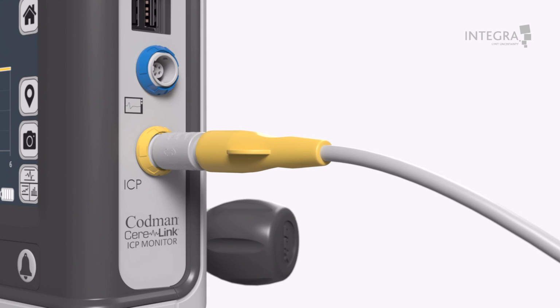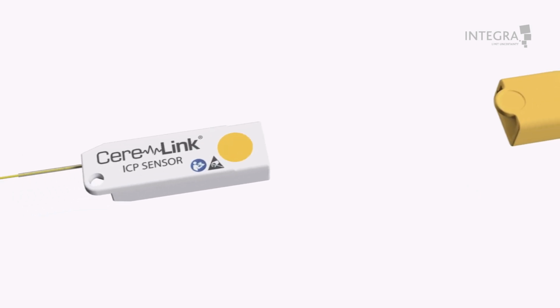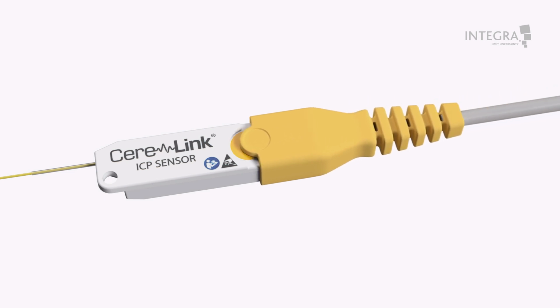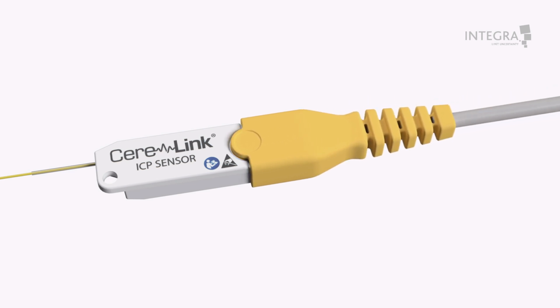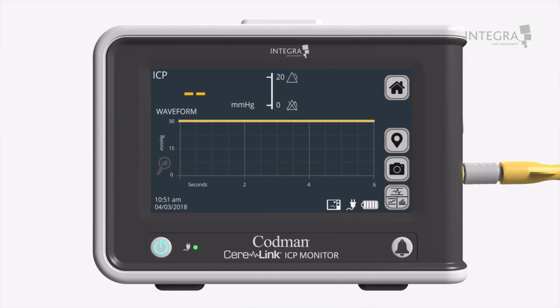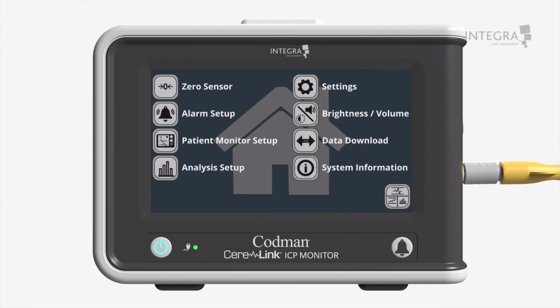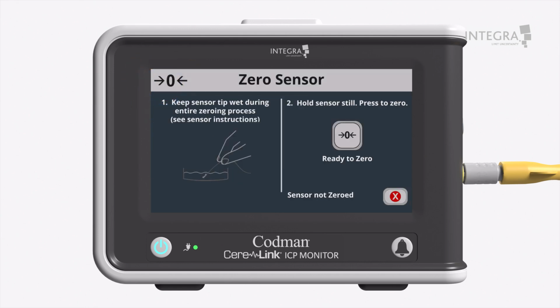If you need to disconnect it at any time, this connection uses a pullback release mechanism and not a twist lock. Whilst maintaining a sterile technique, connect the ICP sensor to the ICP extension cable. Once the sensor is connected, the CereLink monitor will play a sound and will also display a 0 symbol. Press the Home tab on the CereLink monitor. Then press the 0 sensor tab on the CereLink monitor.